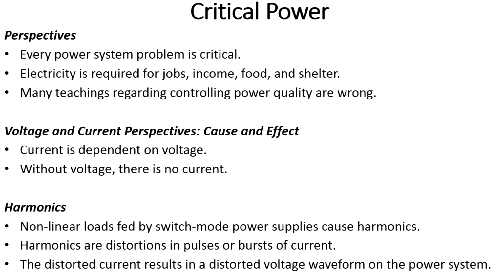They're multiples of the fundamental frequency, and they're harmonics of current. The current being drawn by a load is multiples of the 60 hertz, and multiples are like the second harmonic is double or 120 hertz, the third is 180, the fifth is 300, and so on. And the way that noise comes about is switch mode power supplies are switching back and forth at a particular switching frequency, and that particular frequency of switching, chopping up the voltage waveform to pull bursts of current, is what distorts the voltage waveform.